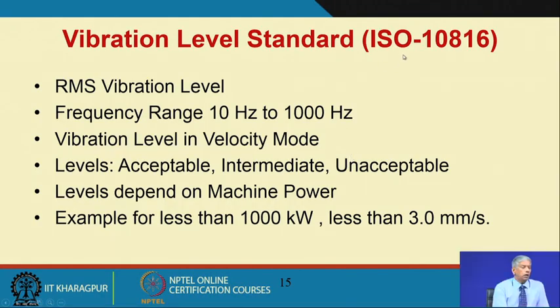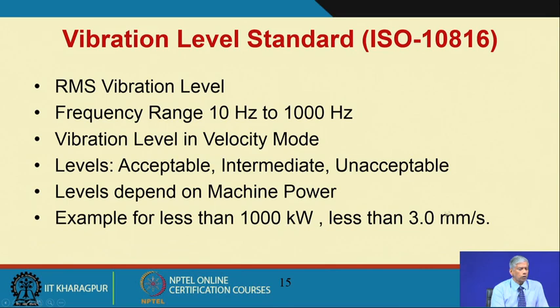ISO 10816 states that vibration level in RMS (root mean square) must be measured, in the frequency range 10 Hz to 1000 Hz, in velocity mode. The standard defines three levels — acceptable, intermediate, and unacceptable — depending on machine power. For example, a machine less than 1000 kW should have a maximum RMS velocity level of less than 3 mm/s. The standard has different parts depending on the type of machine.